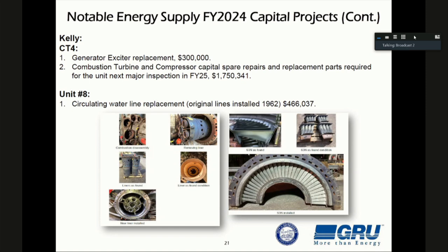The follow-on item is the big ticket item. These combustion turbine components were pulled out of CT3, combustion turbine 3 at Kelly — all the components at the bottom. We have to have those looked at, refurbished, resurfaced, or replaced to make them ready for the next major inspection. Combustion turbine 3 and 4 are identical, so we take the components — we just did the major inspection on combustion turbine 3 — and we have to spend about $1.75 million in '24 to assess those components and replace some if they're beyond their useful life, so they're ready for the next major inspection of combustion turbine 4 in 2025. We spend this money in '24 to make it ready for '25.